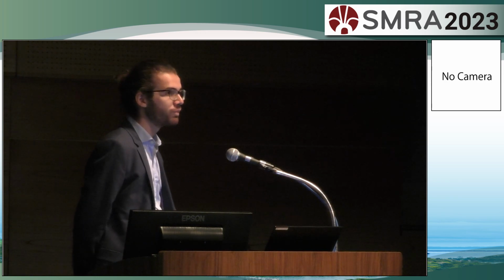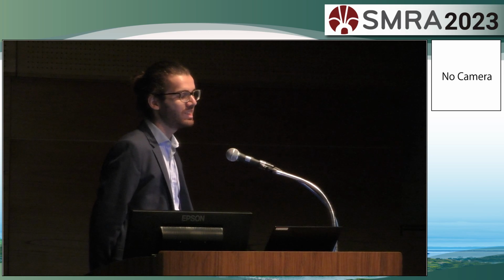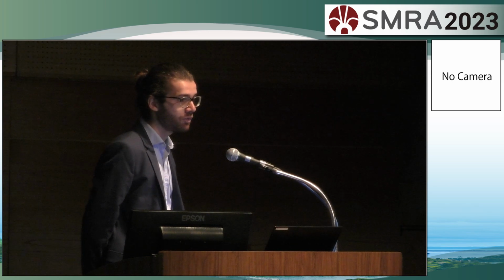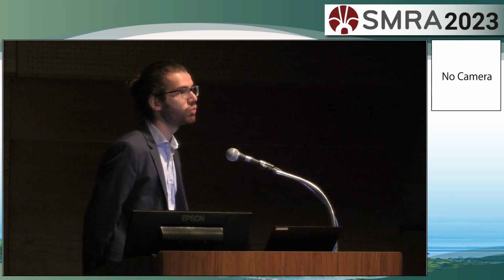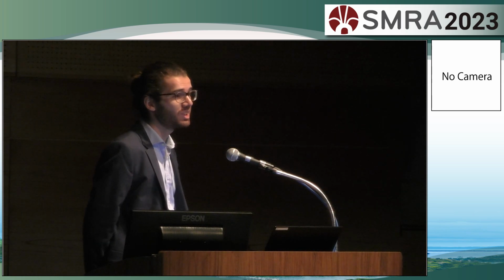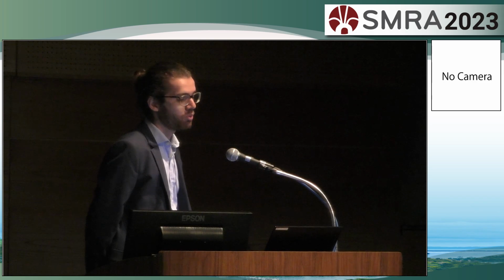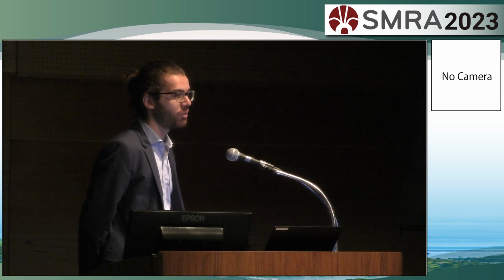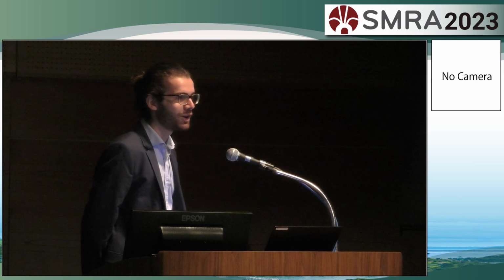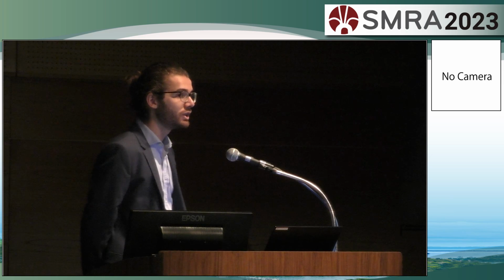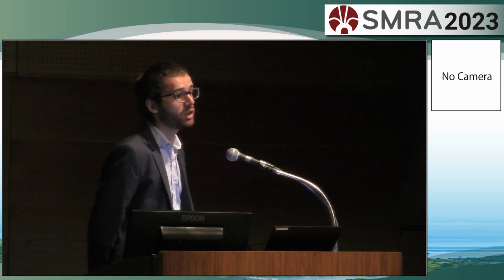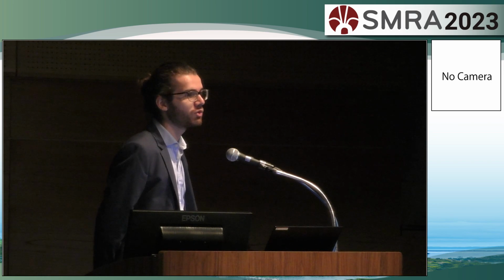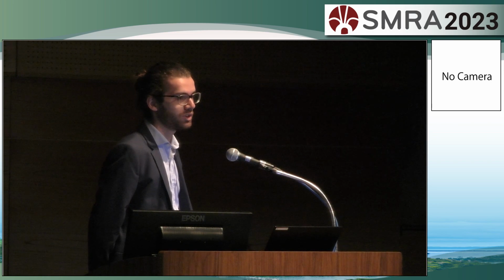Normally with arrhythmia, if we can still detect the cardiac signal from the oximeter, we are normally supposed to still be able to reconstruct our image, but it's true that free-running acquisition always faces the issue of arrhythmia. I never tried, so I cannot give an answer, but in theory it could work if the key is to get the proper cardiac signal, and the oximeter actually will be better than extraction from the SI matrix in my opinion, because it's not that straightforward at all.